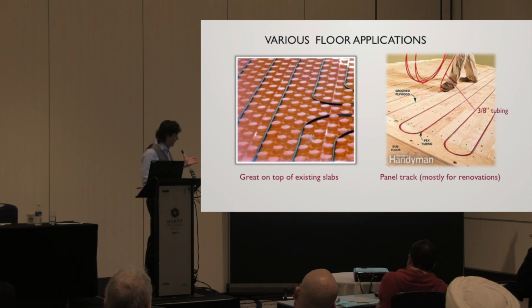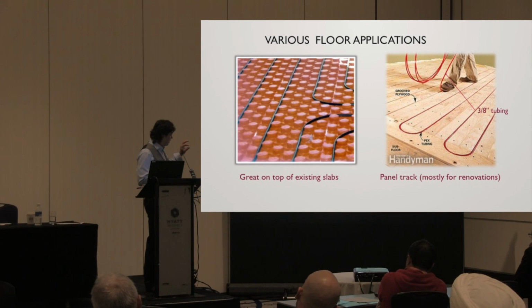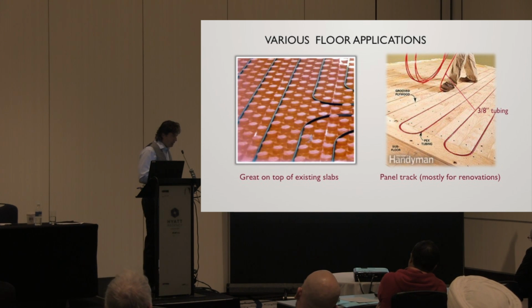I don't know, you add up the cost of the slab and so forth, and you say, well, this is all I'm doing, I'm going to put my hardwood right on this. Maybe it's okay. I don't know. The times I've worked it out, it doesn't make a lot of sense in new construction. Better ways to do it. But in a retrofit, if you want to do a room or two, why not? So here you have thin plywood, so you keep your floor heights low, and now you're using smaller tubing, 3/8 tubing right there. So higher pressure drop, less heat transfer, and normally you put a silicone in there as well, and as you step it down, it keeps the pipe in there. But it's kind of a cool product, actually. I think they use a lot more in the States.